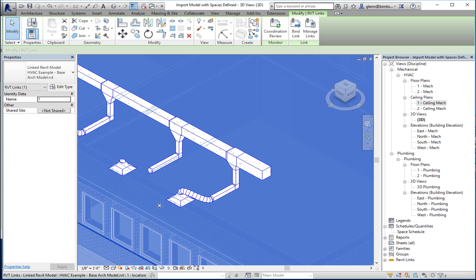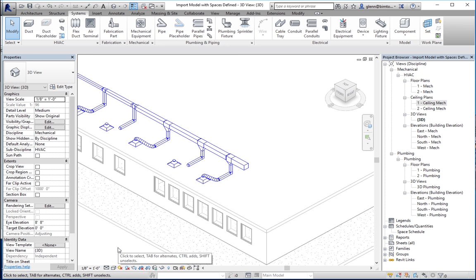Gustavo notes that the main trade-off as velocity increases is noise. He also observed from the tables that circular ducts allow much higher velocity because they have less surface area and are more efficient. In terms of sizing: if 1,000 FPM is making your ducts incredibly large and you can't fit them anywhere, consider raising the velocity — there's a trade-off. If ducts are getting to be 30 by 30 or 40 by 40 inches, that's probably larger than you want, so you may need to relax the FPM limit.